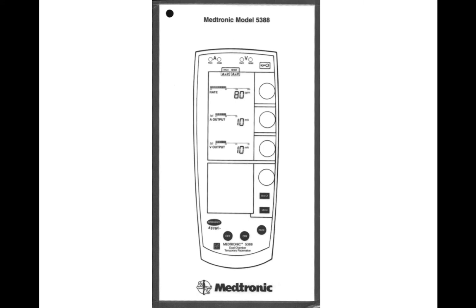Today I wanted to talk briefly about the Medtronic pacemaker that you will find in a lot of critical care settings. This is a dual chamber pacemaker — a temporary pacemaker that works with epicardial wires, temporary transvenous wires, as well as pacer swans. It's a very versatile pacemaker generator that can be used with any of those different devices.